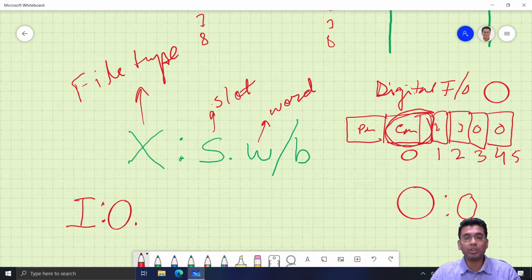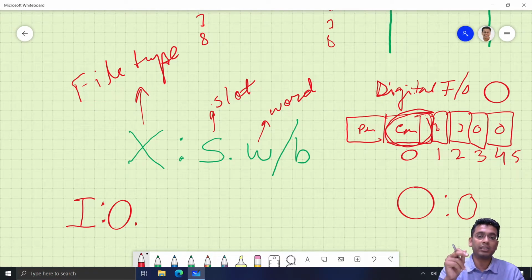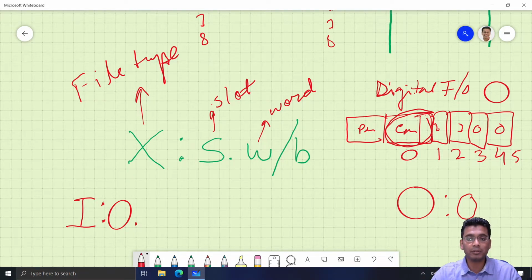And if you have analog input and analog output, I told you that for each you require at least one word of memory to designate one analog input or one analog output. In the case of digital input and output, within one word, if it is a 16-bit PLC, you can incorporate 16 digital inputs, and in one word you can also incorporate 16 digital outputs. The word numbering also starts with 0, 0 being the default.